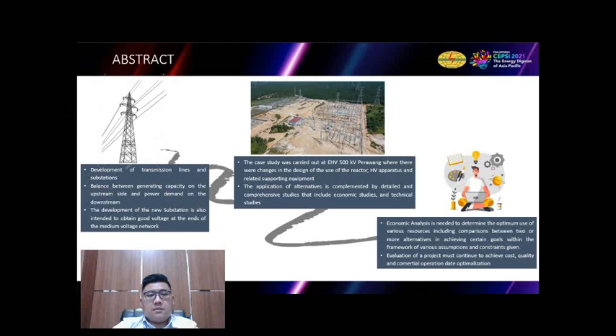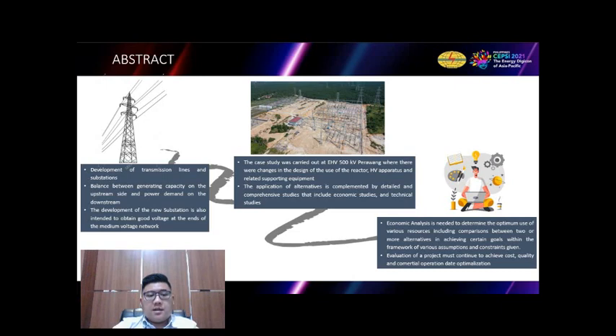First of all, it's all about the abstract. The development of transmission line and substation are generally to achieve the balance between generating capacity on the upstream side and the power demand on the downstream side. The development of the new substation is also intended to obtain good voltage at the end of the medium voltage network. The case study was carried out at EHV 500 kV Perawang, where there were changes in the design of the use of the reactor, HV apparatus, and the related supporting equipment.